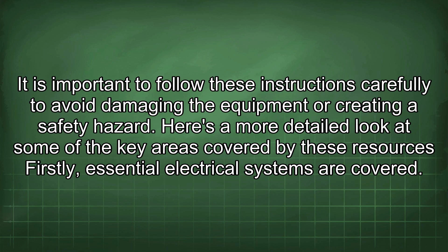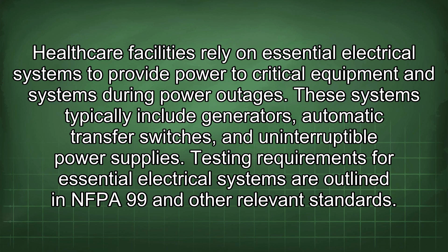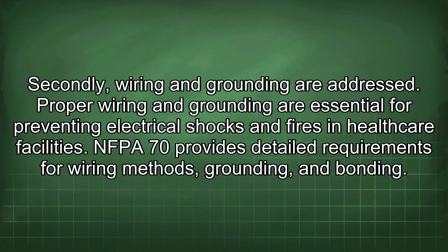Firstly, essential electrical systems are covered. Healthcare facilities rely on essential electrical systems to provide power to critical equipment and systems during power outages. These systems typically include generators, automatic transfer switches, and uninterruptible power supplies. Testing requirements for essential electrical systems are outlined in NFPA 99 and other relevant standards. Secondly, wiring and grounding are addressed. Proper wiring and grounding are essential for preventing electrical shocks and fires in healthcare facilities. NFPA 70 provides detailed requirements for wiring methods, grounding, and bonding.